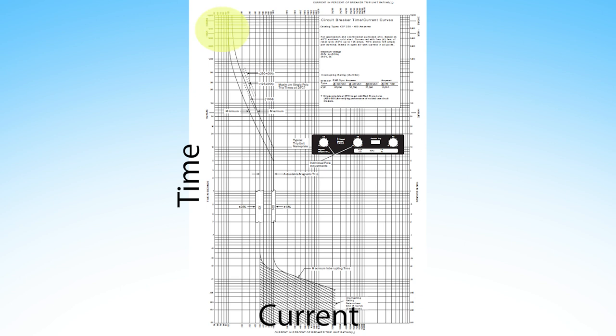It's obvious at a glance that the lower the current the longer it takes to trip. This is common for most breakers and fuses. The intended use of the device determines the desired curve.